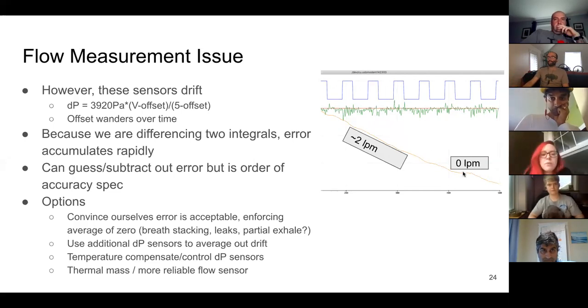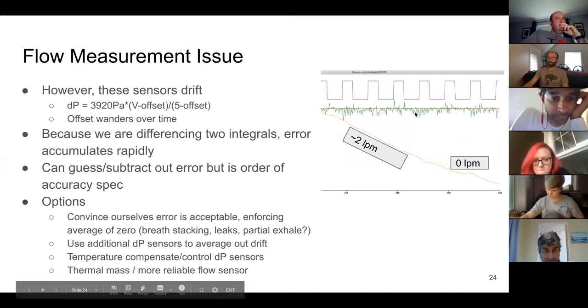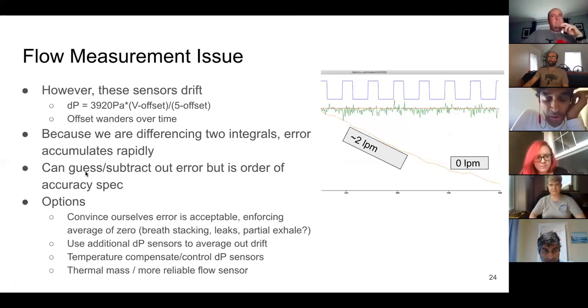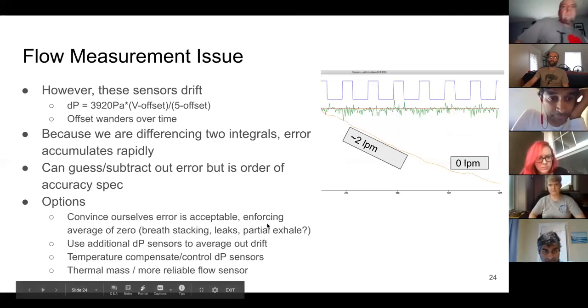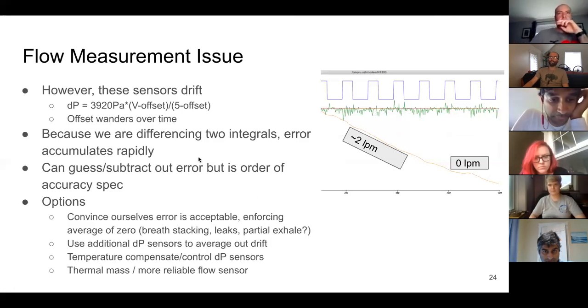The problem is it changes, and it can change pretty quickly, even over the course of seconds. With your finger, you can drive it to be flat, but if the patient's breathing and volume is also changing, it's really hard to cancel out that integral without enforcing volume compliance. So whether the issue is a better pressure sensor, a redundant differential pressure sensor, or a different flow measurement solution in general, that's something we need to work out pretty quickly.